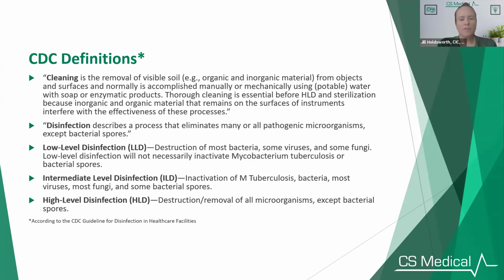So not an option. When you're out there auditing these processes or observing, you must make sure that cleaning step is done and it's done well. If it's not, you are going to compromise the high-level disinfection process. So when you're disinfecting something, this is obviously that step that removes the pathogenic microorganisms. But then when you take it a step further, for some of you who aren't as familiar with some of these terms, low-level disinfection is going to be using your normal disinfection wipes, something that you're using on an everyday basis. And then your high-level disinfection is going to be that 6-log kill. So we're destroying and removing all those microorganisms.